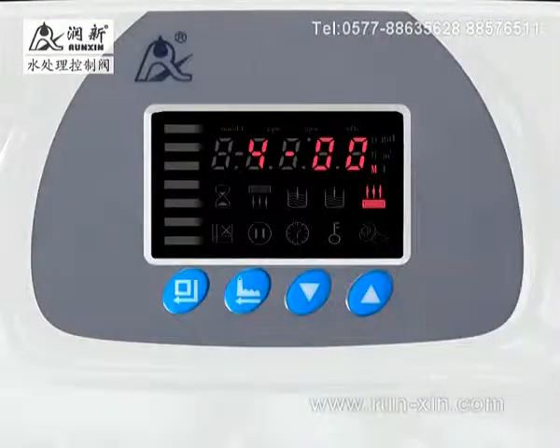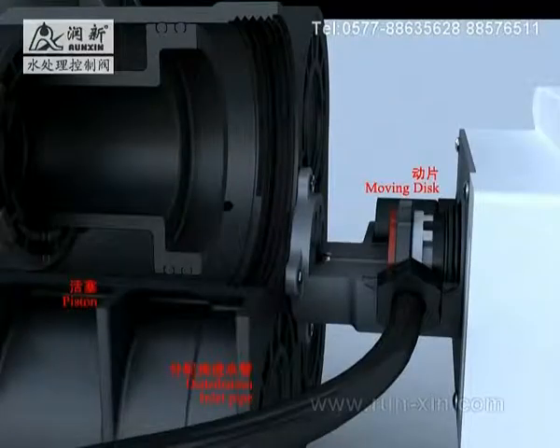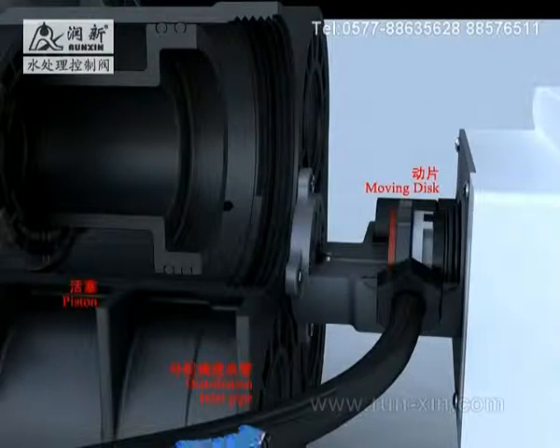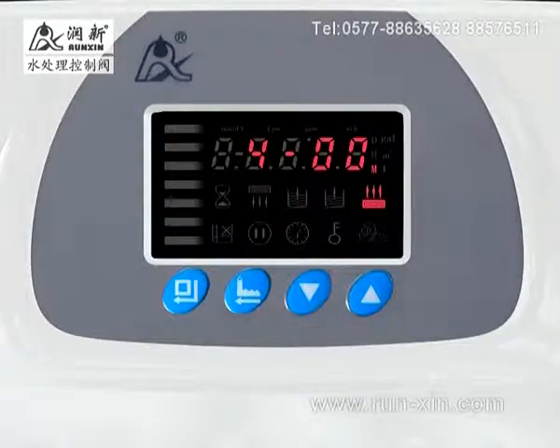When faster rinse time reduces to 0, the motor controlled by the main control board rotates, which changes the relative angles of the moving disc and fixed disc. Small parts of raw water through the water inlet go to the distribution valve and 4 chambers to control pistons opening or closing to change its flow channels. When it arrives at brine refill state, the symbol of brine refill lights.